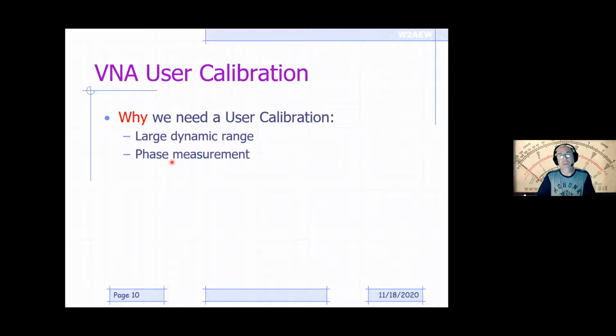For example, if you want to make a measurement at the input port of your device, you still have to connect it up to the VNA. The VNA doesn't know how long that interconnect is, so you can't predict what the phase would be at your DUT. By doing a proper user calibration, you can establish what we call a measurement plane, so that the phase is essentially normalized right to the connection points of the device under test. And so all the phase and delay associated with the interconnect getting to your device can be calibrated out. Okay, so that's also part of what happens when you do a user calibration.